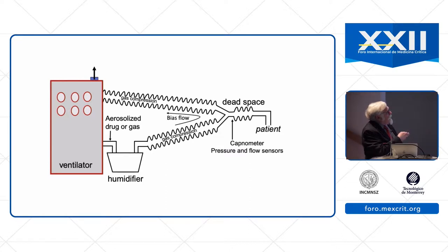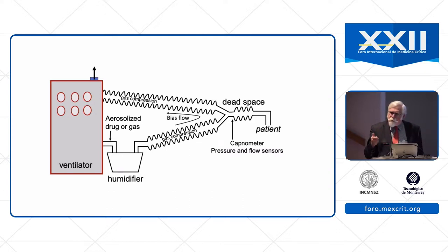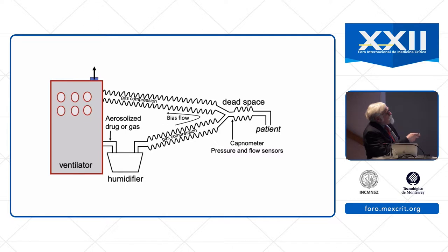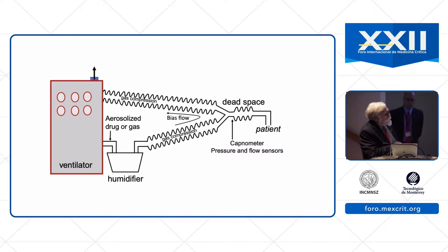We can deliver aerosolized drugs or gases by injecting them into the ventilator circuit. It's important to appreciate the amount of dead space, which is the volume of the circuit between the Y connector and the patient. The volume of dead space in the circuit will effectively reduce the alveolar ventilation for the patient. We want this dead space to be as small as possible. We want to avoid placing tubing between the Y connector and the patient, and avoid adding other devices to the circuitry which could increase dead space and reduce effective ventilation.